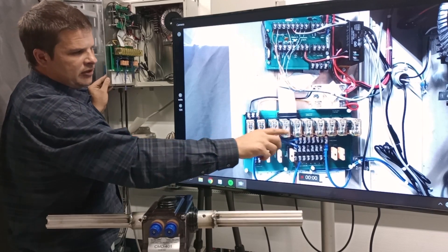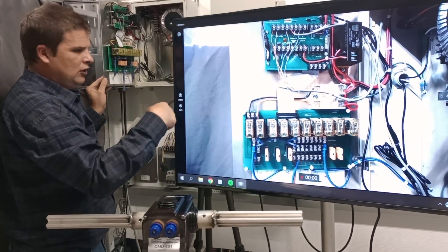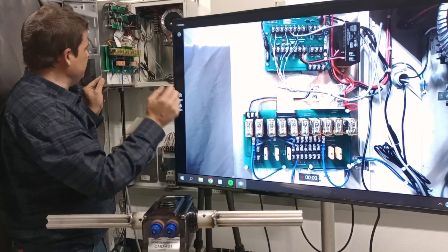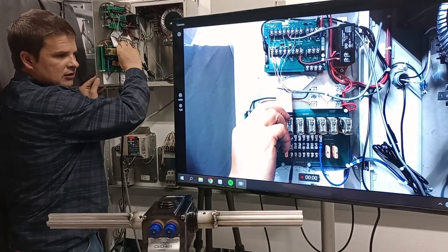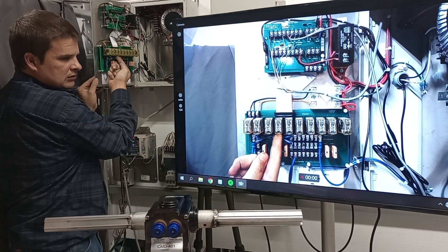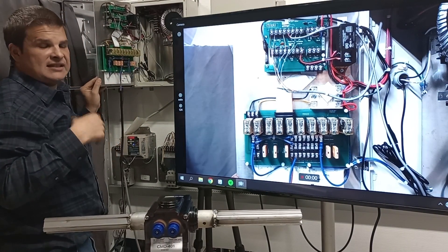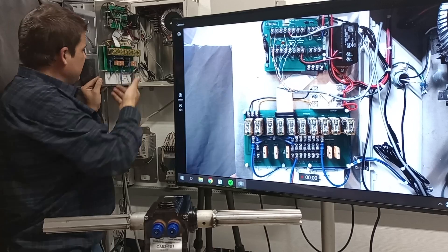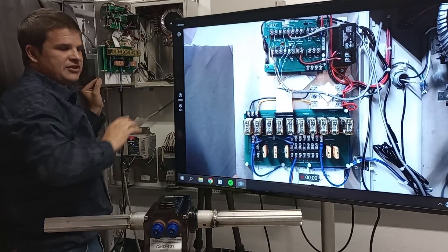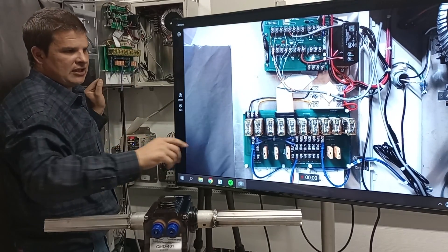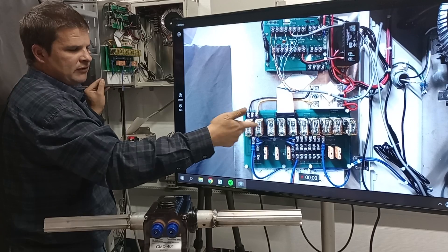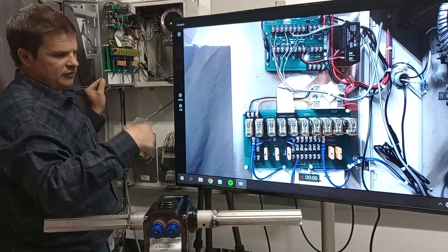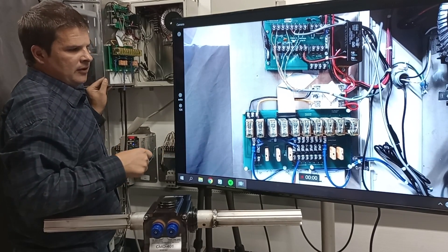And these yellow cubes are the relays. They have overrides on them. You can mechanically test things by pressing on the little green button, and it actually sends electric out, or it doesn't even have to rely on the controller to do it, because you're manually moving the contact.